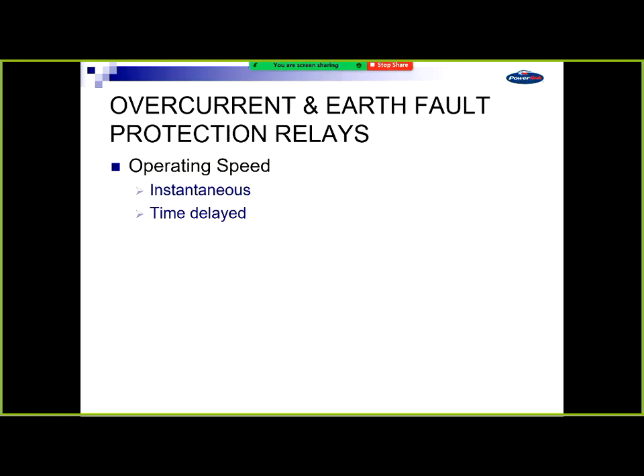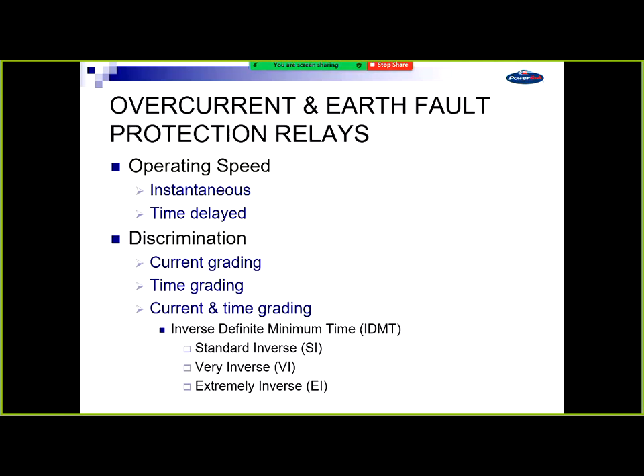There's a number of ways you can use it. The overcurrent can be instantaneous, or you can have it time delayed. You can discriminate on current, time, or very common is current and time, which is your inverse definite minimum time, IDMT. And the most common type of IDMT is a standard inverse, but there's many different curves. British, IEC and ANSI, I think, is the other one, the American one. If you look at the relay manufacturers, they say the overcurrent element inside their relay can do about 15 different curves. Still the most common is a standard inverse.